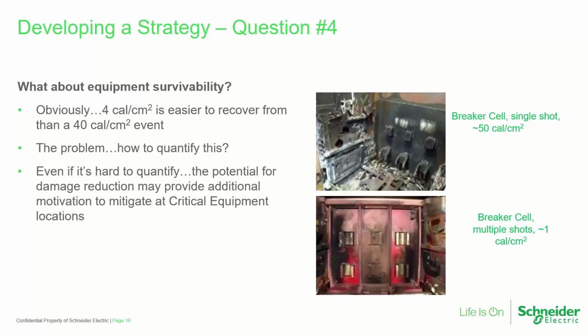It could also drive you away from things like maintenance switches. What state is the maintenance switch in 99% of the time? Maintenance mode is off. You're not protected. Maintenance mode is on only when somebody's actually doing work on the gear. And so most of the time, you wouldn't get the benefit of potential additional equipment protection as well.